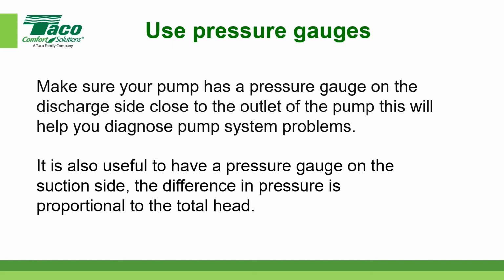Rich has a funny story about pressure gauges. There were two on a job one time, and one wasn't working correctly or read zero, and they thought there was a problem with the pump. He said, well, take the one that's working and put it where the one that's not working is, and take the other one and flip it around. And it turned out the pressure gauge was bad, but nonetheless, put them on there, put them in your details.